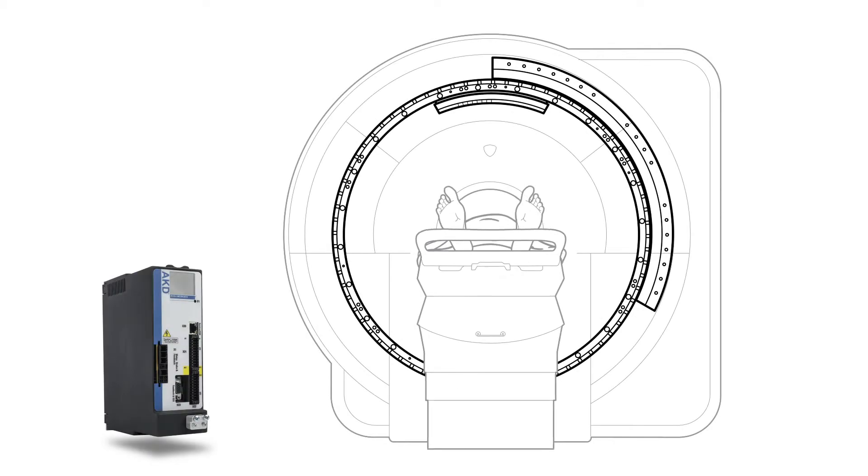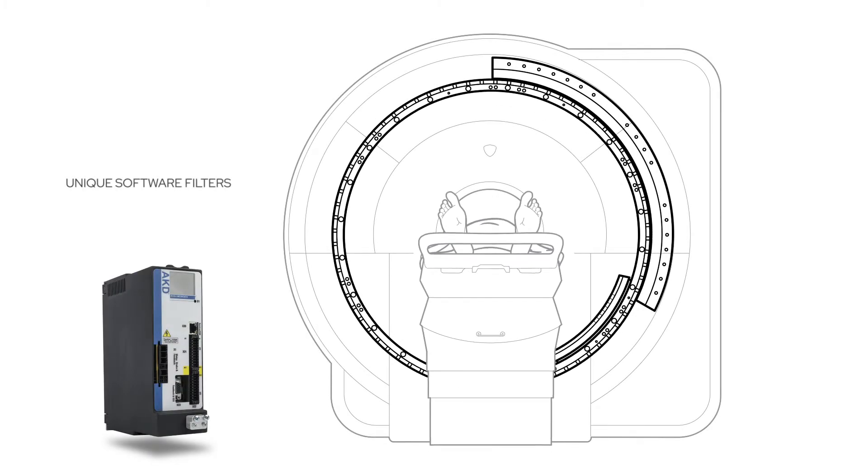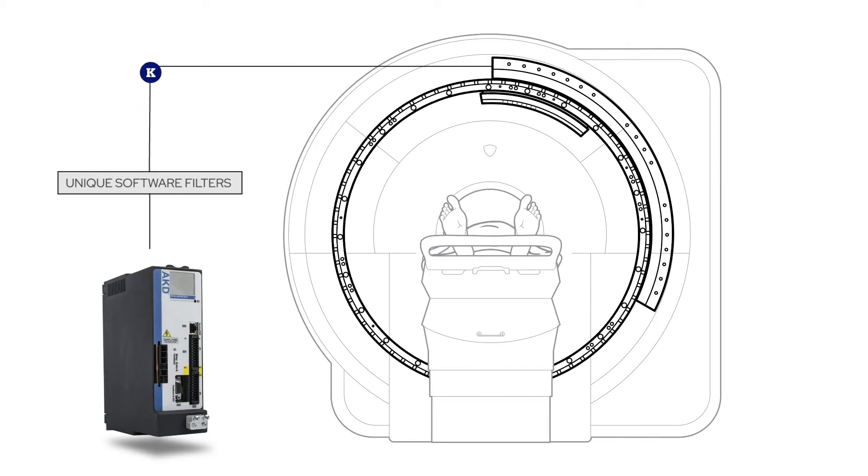Kollmorgen applies unique filters that allow for more precise control over the large rotating mass of an imaging gantry. When something that massive moves, it causes secondary motion in the frame of the machine. Our software filters compensate for secondary motion and even human movement.